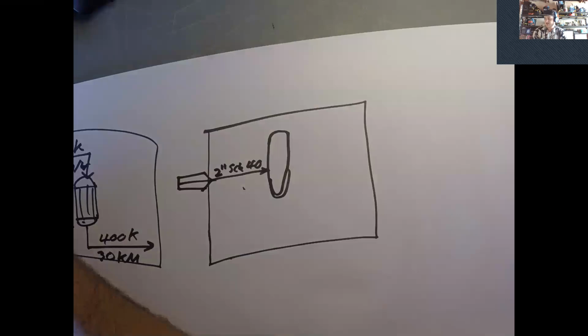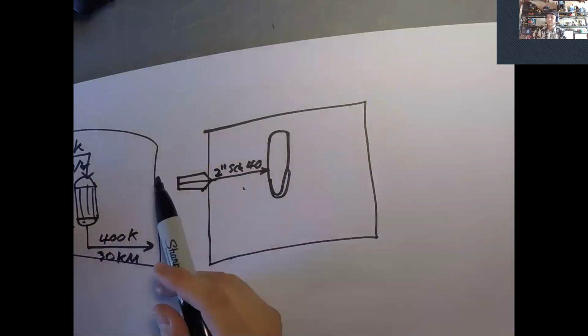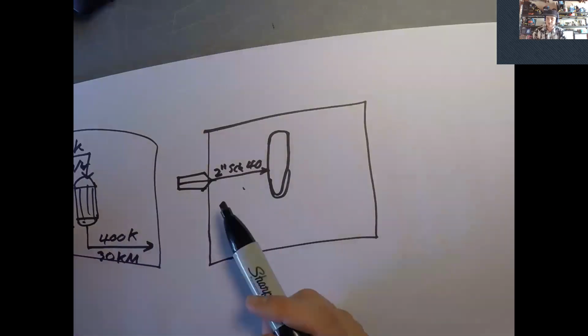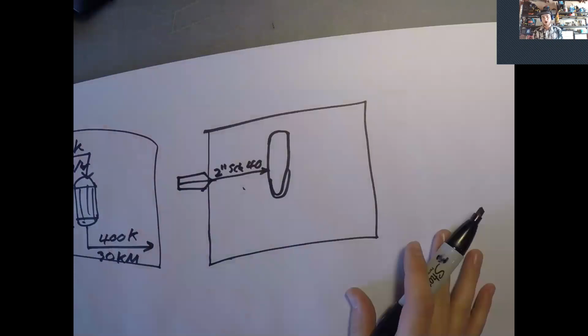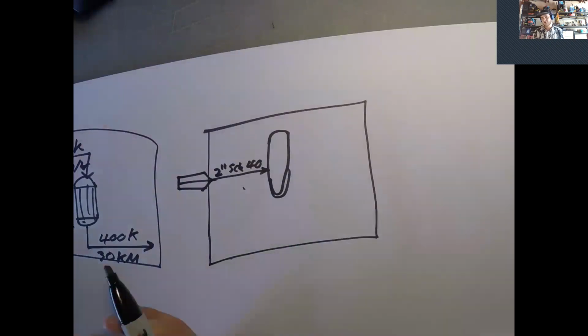because anytime this gets reworked, if your product stream changes or a regulatory agency is coming in and they see that spec is called out and you're not meeting that spec, then all of a sudden you have to do drawing updates and it becomes a big nightmare. So the purpose of a P&ID is really to call out, like, hardware wise, what do I have available to me?